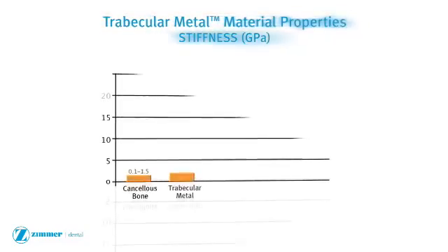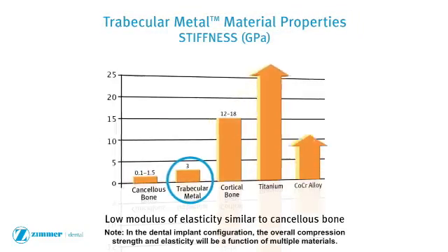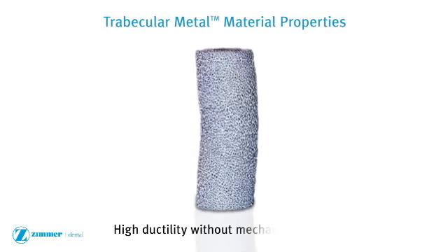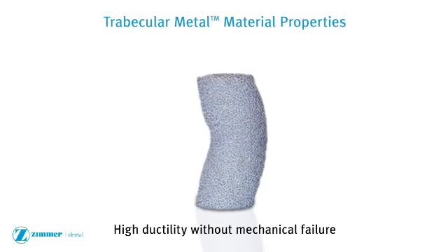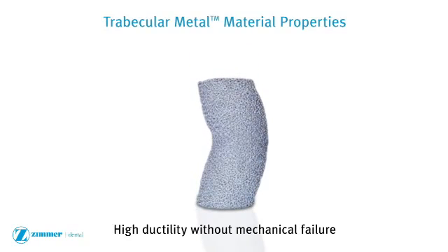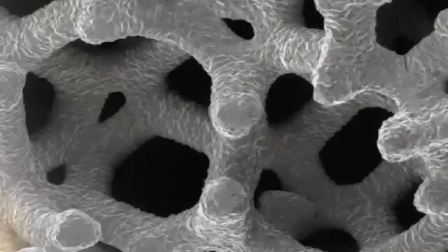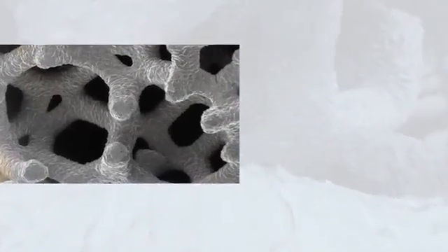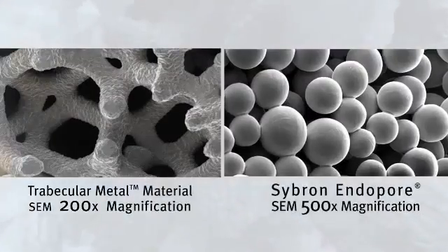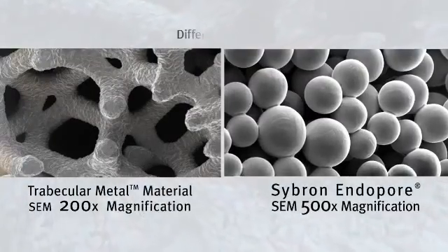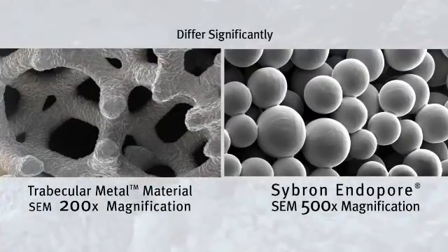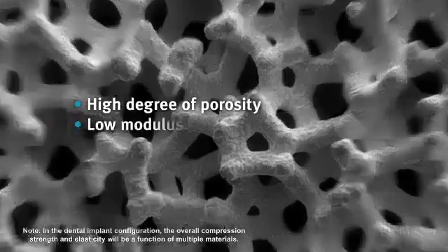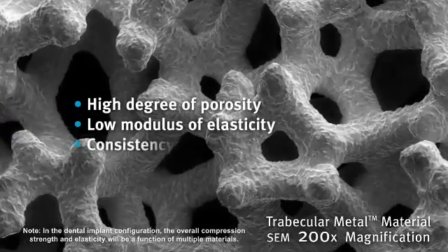Trabecular metal material has a low modulus of elasticity similar to cancellous bone. In compression testing, trabecular metal material exhibits high ductility without mechanical failure. While other manufacturers have tried to mimic the attributes of trabecular metal technology, sintered bead and other conventional porous coatings and materials differ significantly from trabecular metal material's high degree of porosity, low modulus of elasticity, and consistency in pore size and shape.